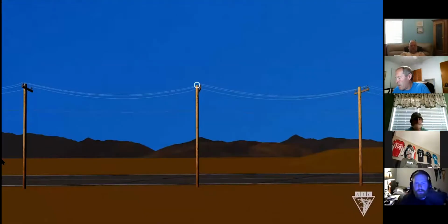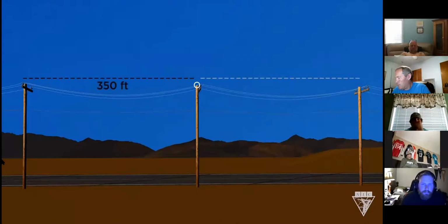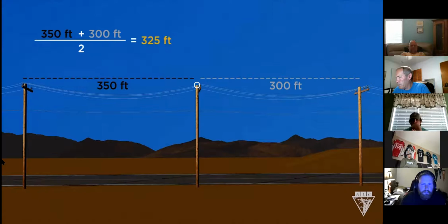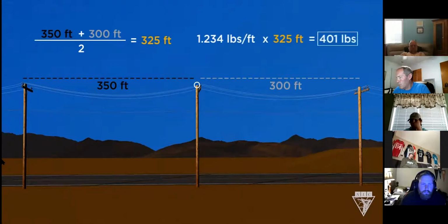If you're lifting the line at this point, get the span length on each side of the pole. So this one's 350 feet and this one's 300 feet. Now I'm going to add these together and divide by 2, and I get 325 feet. Next, find the weight per foot of the conductor you're working with. You can ask the manufacturer or engineering department if this number is not on the work order. This one is 1.234 pounds per foot. Just multiply these together, and that's the weight that we lifted.